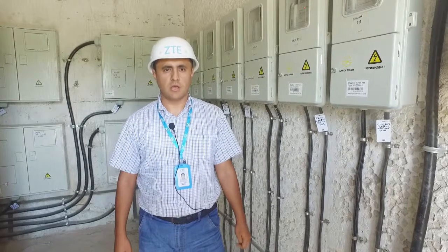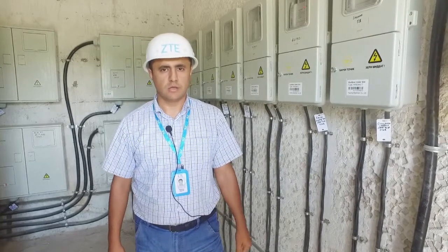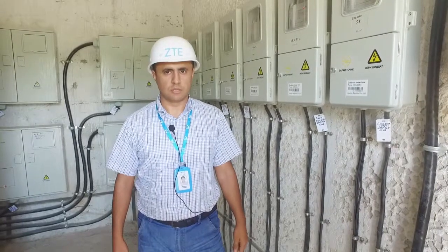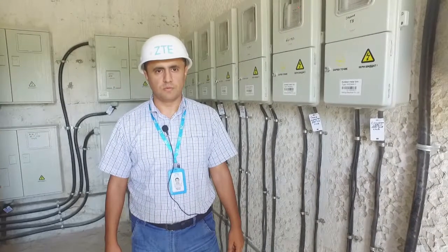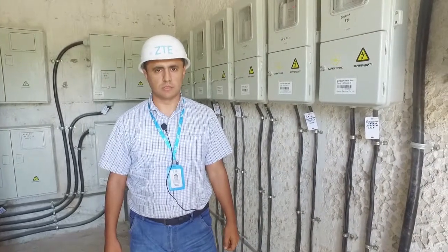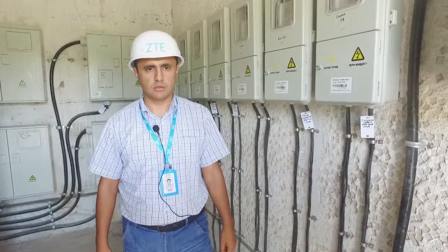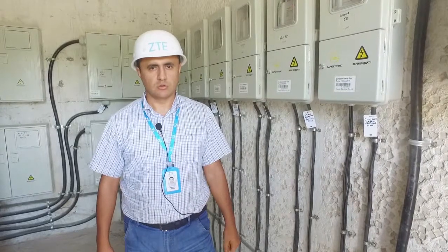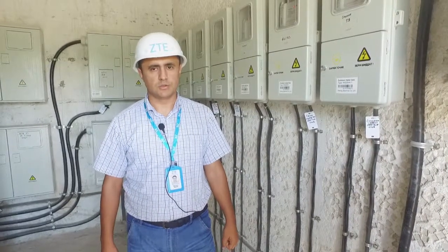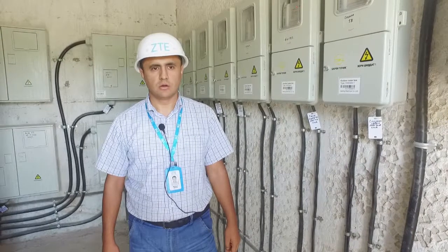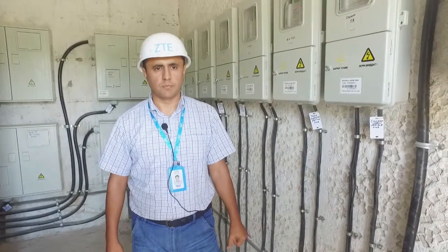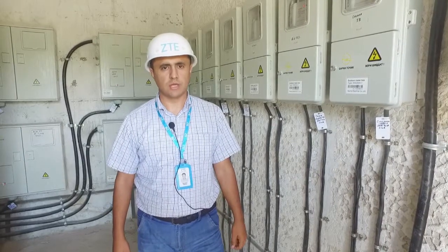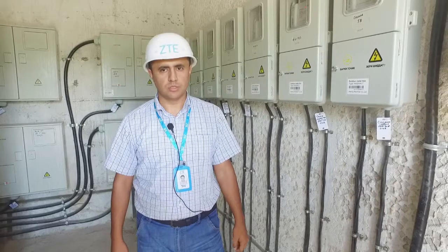Before we start any energy meter installation for any type of consumers belonging to this transformer, first we have to install the bulk meter at the transformer point to calculate the total energy consumption of all the consumers. It also makes registration of new consumers easier, as the PLC will be running at this time. The PLC running is important during new meter registration in the AMI system when we are using PLC communication.